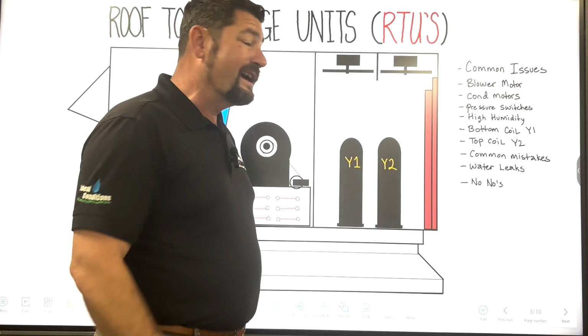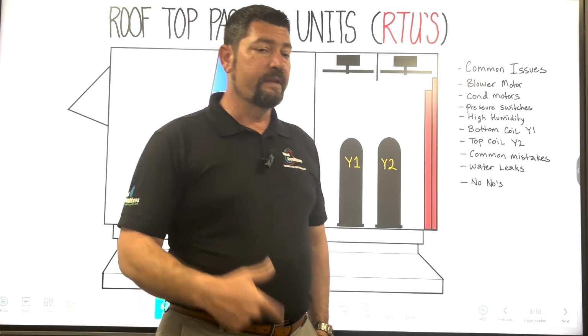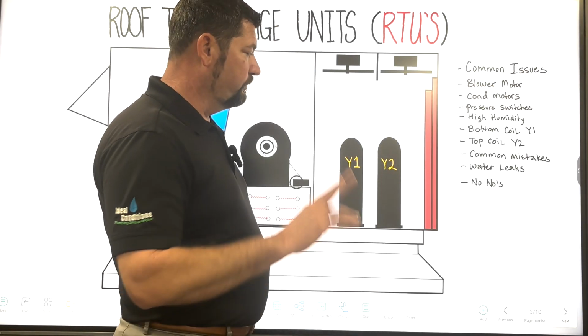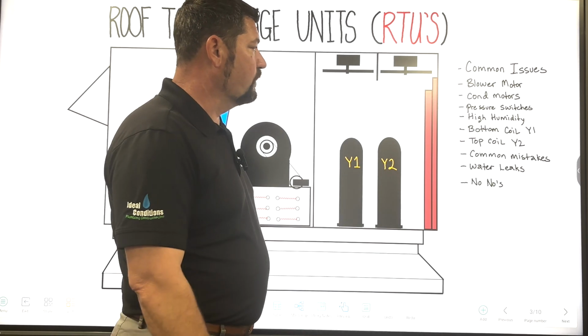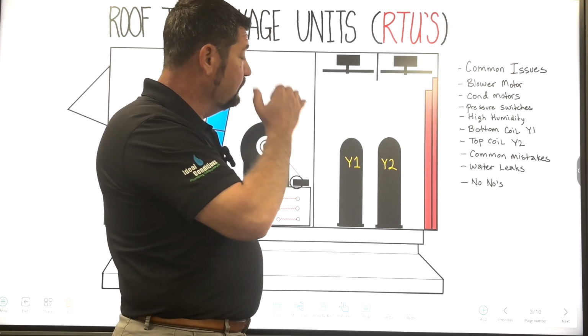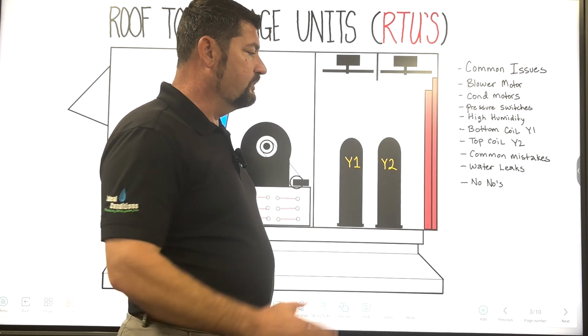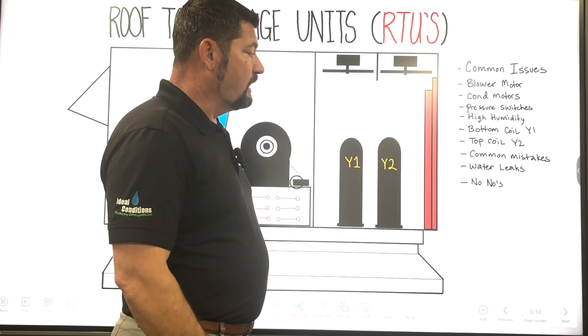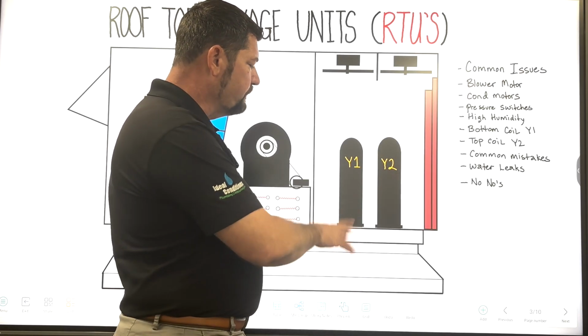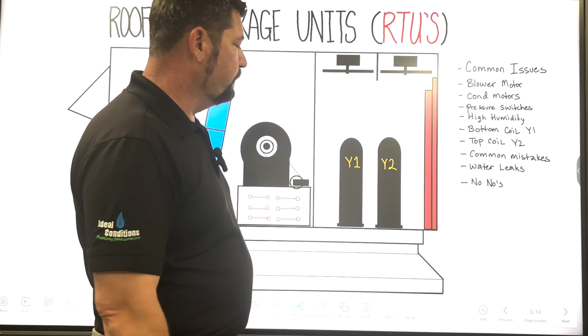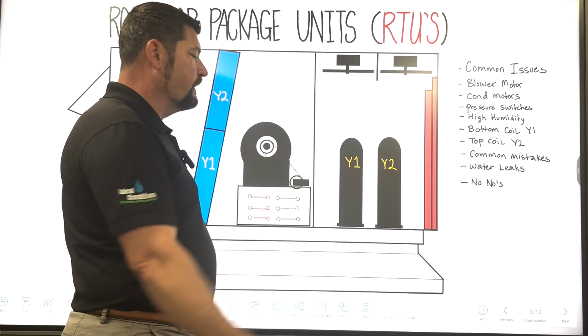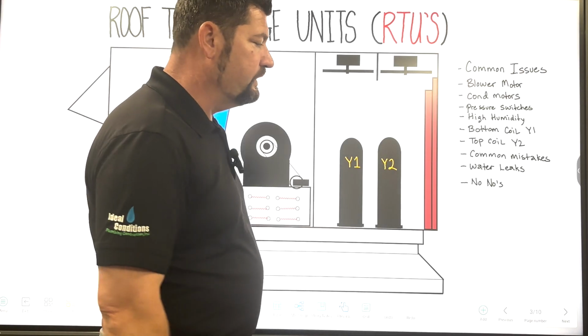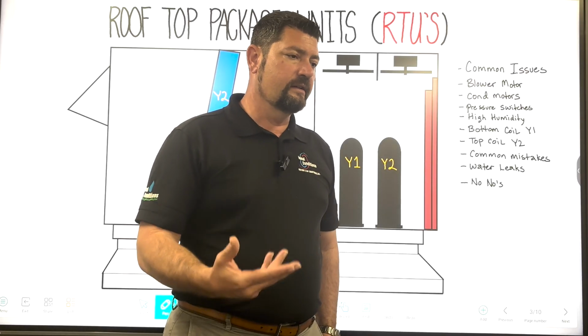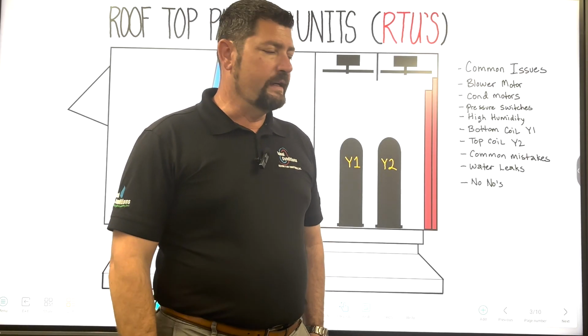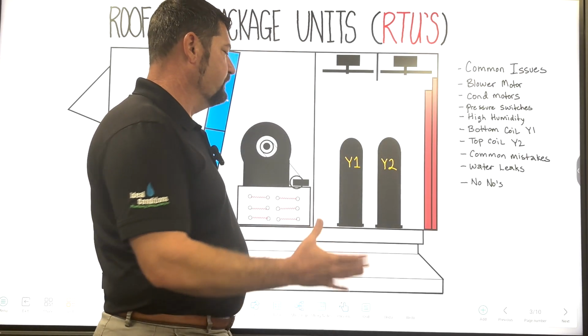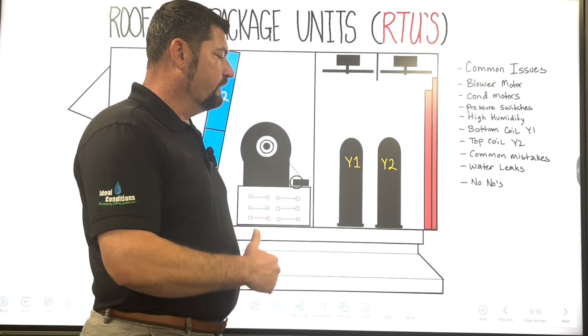However, not many people are actually going up there to even inspect the equipment that has been supposedly cleaned or worked on correctly. So we see a lot of these rooftop units that are just in disarray. They have a lot of issues. The amount of money that it costs to replace one of these is pretty up there, and they're not readily available. When you get into these higher tonnages, they're just not available as fast as you need them. So it's very important to make sure these things are running properly for your client.